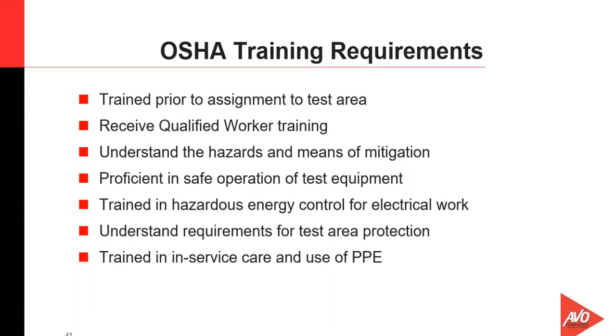Understand the requirements for test area protection to be able to identify what a safe test area would look like, how to set it up, what the requirements are, and how to maintain that. And then trained in the in-service care and use of all the PPE items that would be used in the system. There are other training requirements, but these are the basic requirements that a qualified worker would have to work in a testing area. One of the big issues here is not only how to do the test, but how to analyze the data you get. So that might be a serious issue too, as far as training would be concerned.